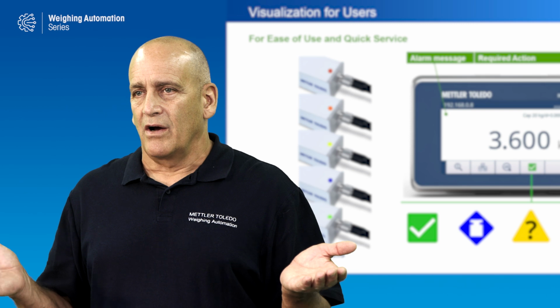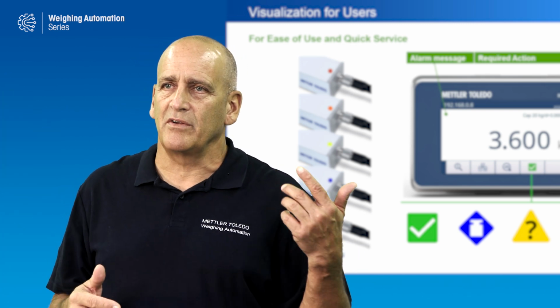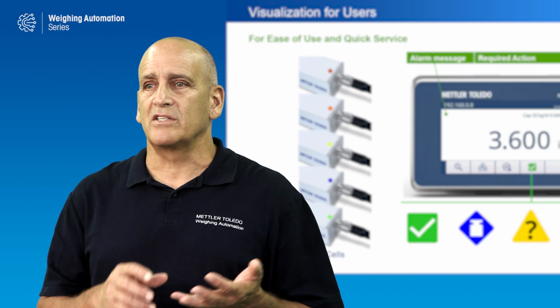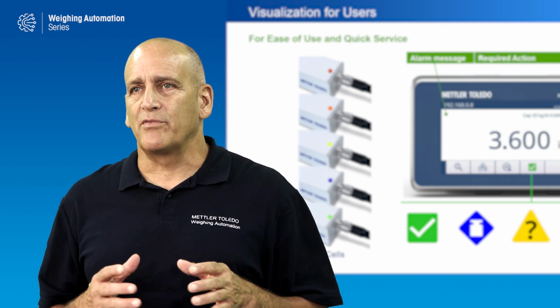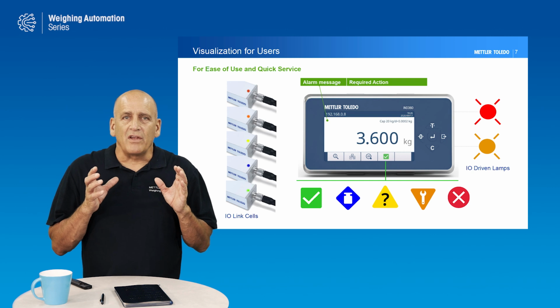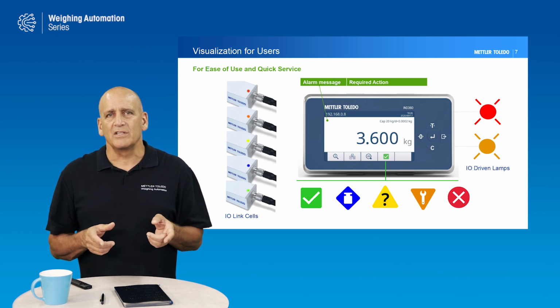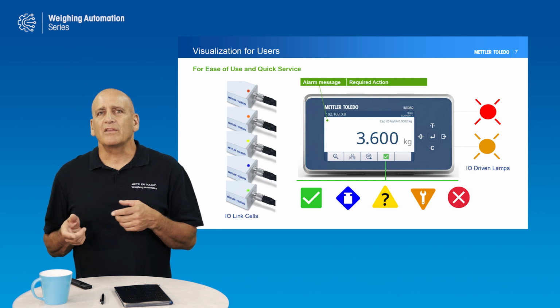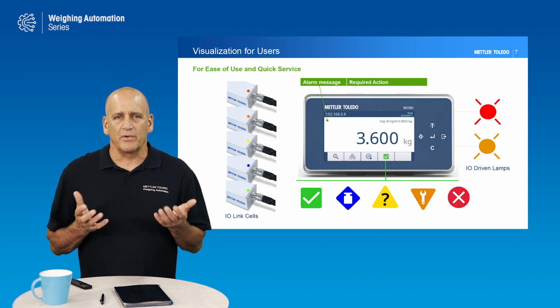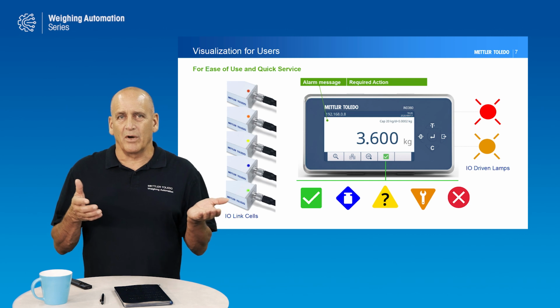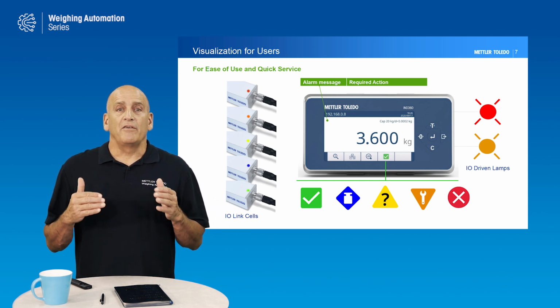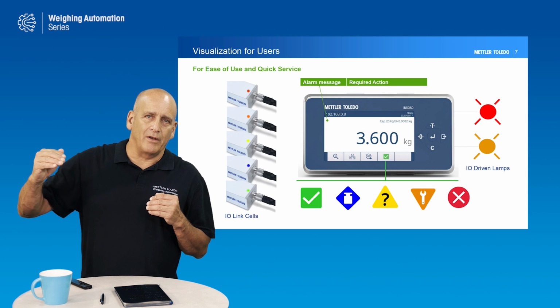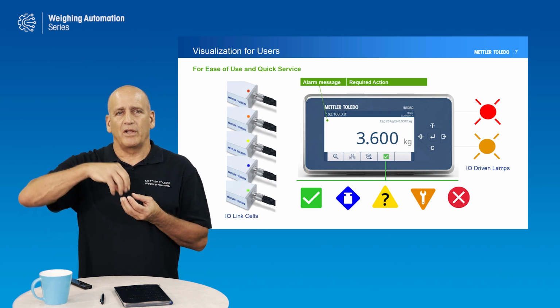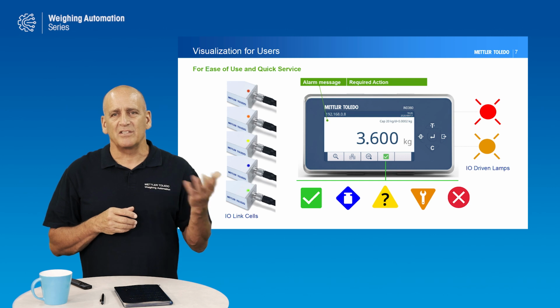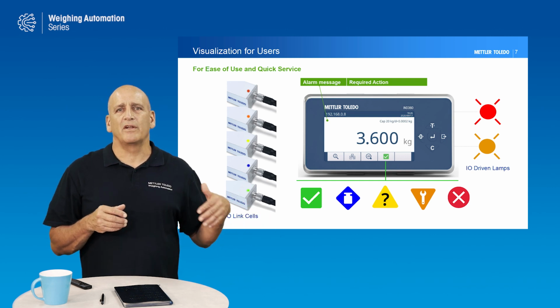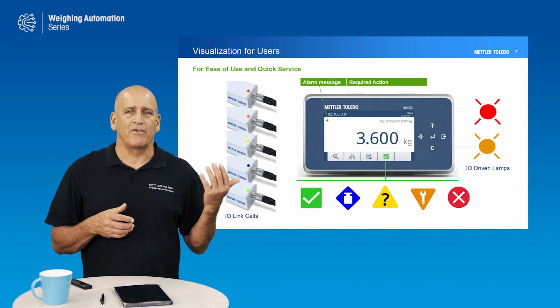If you look at our terminals, our future terminals will have this on the display. So if there's an operator there, they can see, okay, it's a red alarm. And if you look into the top of the display, we don't have it in this graphic, but we will send a message of what the alarm actually is and what actions need to be taken to make that alarm go away. So this is a really cool feature because we're not only going to tell you that you have a problem, we're going to tell you what you have to do about it. And then finally, if you want to slave one of the alarms to an output, you can indicate a red or an orange alarm with a neon light with the output of this device. Now this device has a limit on the amount of I/O points, but in our higher I/O count products, you could do all 5 levels.